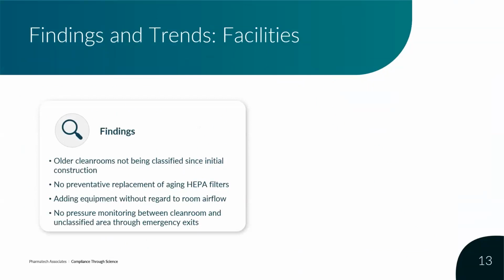In the case of facilities in particular, there are a number of older clean rooms that have not been reclassified since initial construction, or some of the aging HEPA filters have not been proactively replaced. There's also adding equipment without regard to room airflow - continuing to make changes and evolve the space without consideration of critical elements related to aseptic processing. And also the lack of pressure monitoring between the clean room and unclassified areas like emergency exits. These in particular may reflect back more on some of the older facilities.